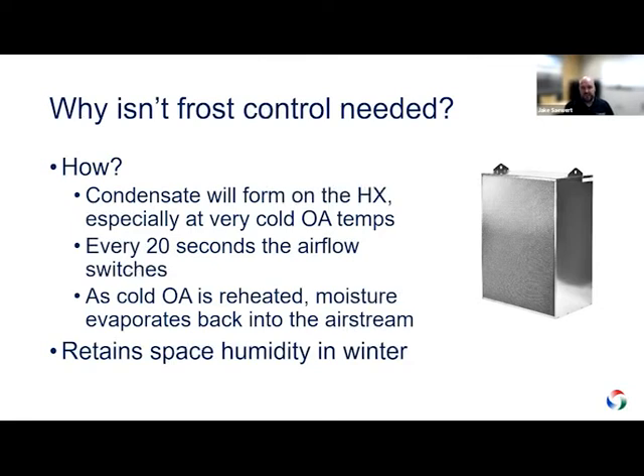Now, there is an ambient temperature where we do like to start talking about frost control. It's about -40. Below that, what we see and what ACCUBLOC has seen is that you can actually get frost and accumulation on the exhaust airstream side, not the heat exchanger, but actually downstream of it. It just becomes so cold that it has to be addressed. But you know, in Colorado, I don't think we're looking at temperatures that cold.